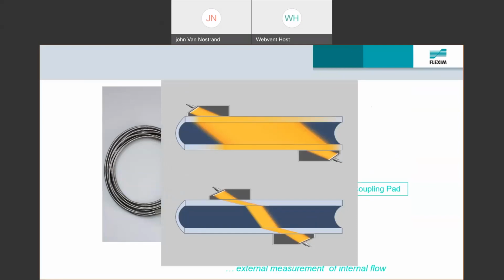I also mentioned earlier that we use a couple of different styles of measurement, lamb wave versus shear wave. If you were to visualize the energy, the lamb wave, which is depicted at the top, is kind of more like a floodlight, whereas the shear wave is more like a spotlight. So we're focusing the energy. The lamb waves are typically used in some chemical applications, and a lot of the time it will be gas applications, air measurement, compressed air, things like that. And the shear wave is for liquids.